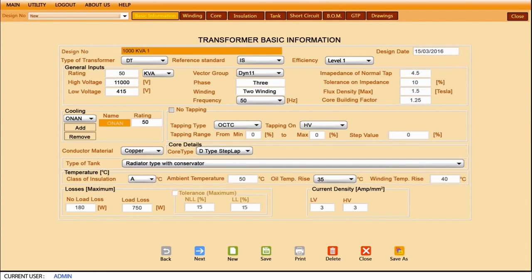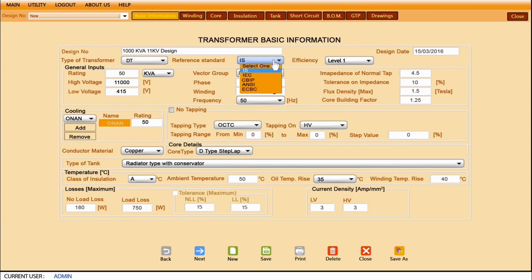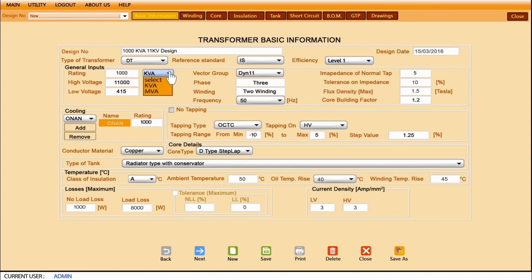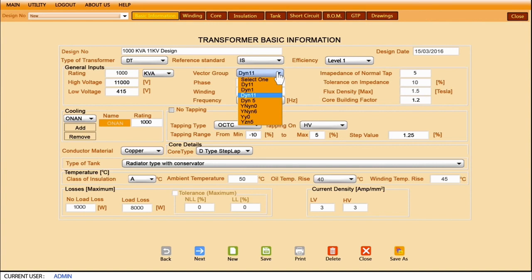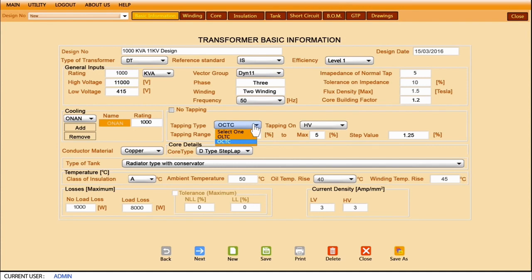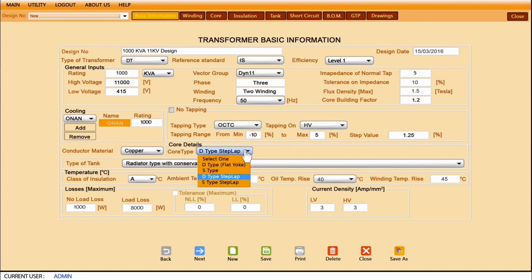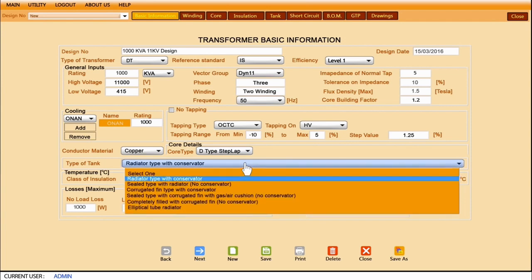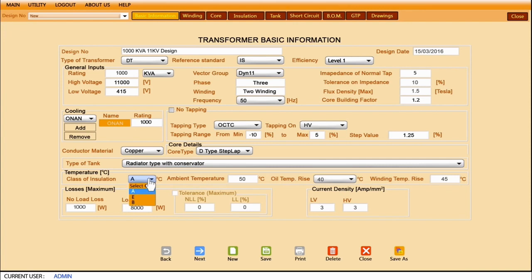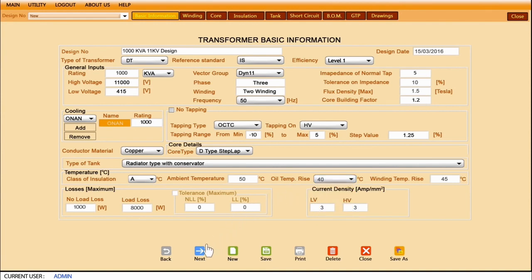Firstly, the user enters the design number, reference standard, efficiency, and rating of the transformer to be designed. Then vector group, frequency, tapping required or no tapping, and conductor material are entered. The user also specifies core type, type of tank, class of insulation, and can edit ambient temperature, oil temperature rise, and winding temperature rise.